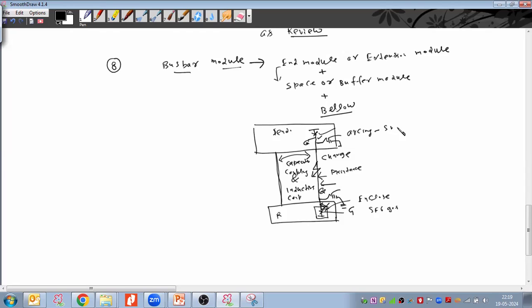If the small arcing happens, this arcing will be inside the GIS, inside the gas. So what will happen? Your gas insulating property gets weak, right? Because if the arcing is happening inside the gas, there would be decomposition in the gas, right? So due to that, the byproducts will come from the gas, and it may weaken the insulating property as well.